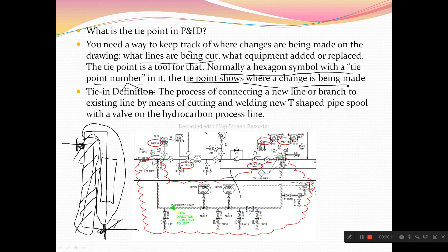Whichever existing lines are connecting to your equipment nozzles — those nozzles and lines will become tie points. Normally, a hexagon symbol with a tie point number in it shows where the change is being made. Wherever you see a hexagon symbol in the P&ID, it means a new line is being added to your existing line. The definition: the process of connecting a new line or branch to an existing line by means of cutting and welding a new T-shaped pipe spool with a valve on the hydrocarbon process line.